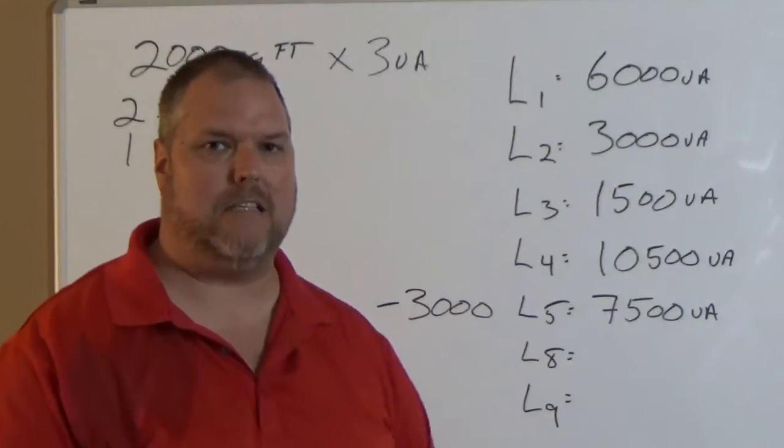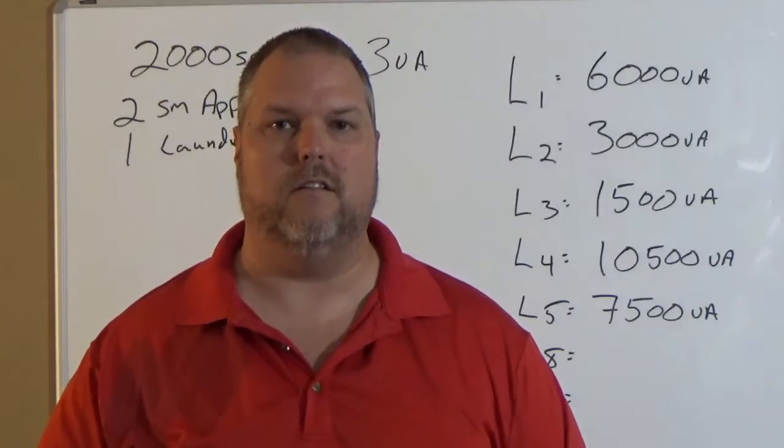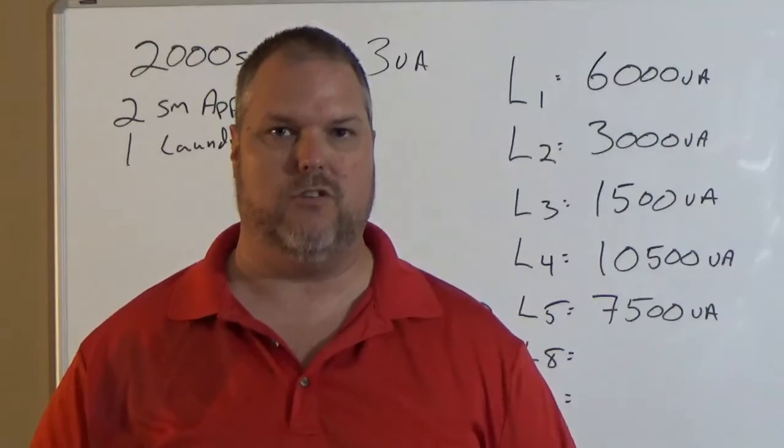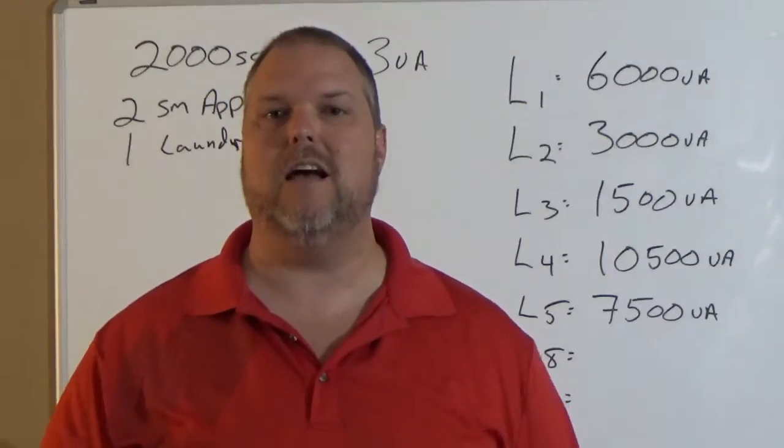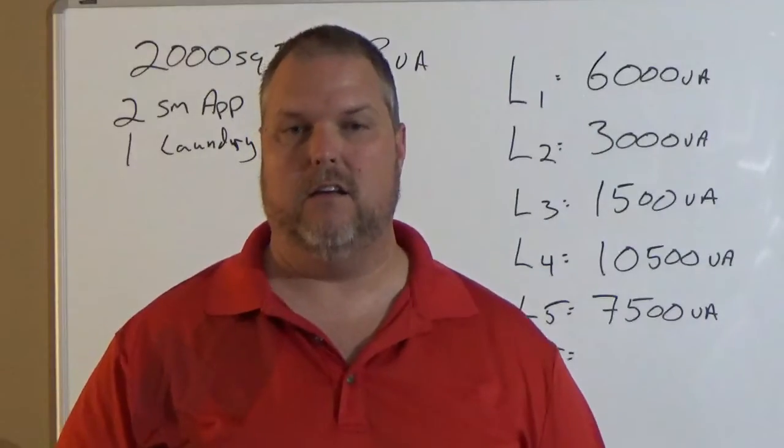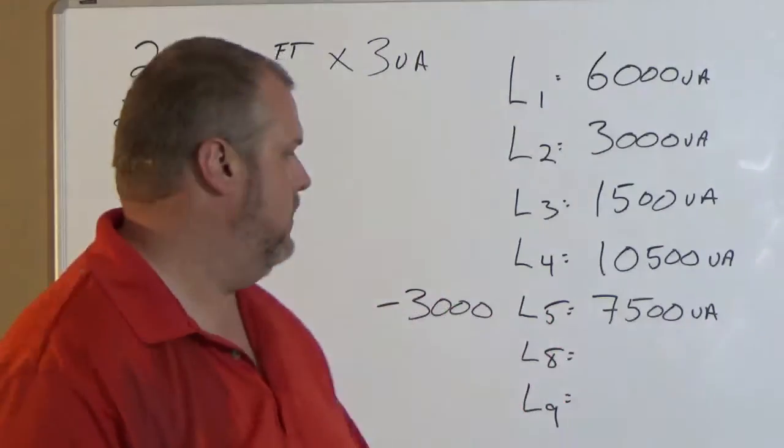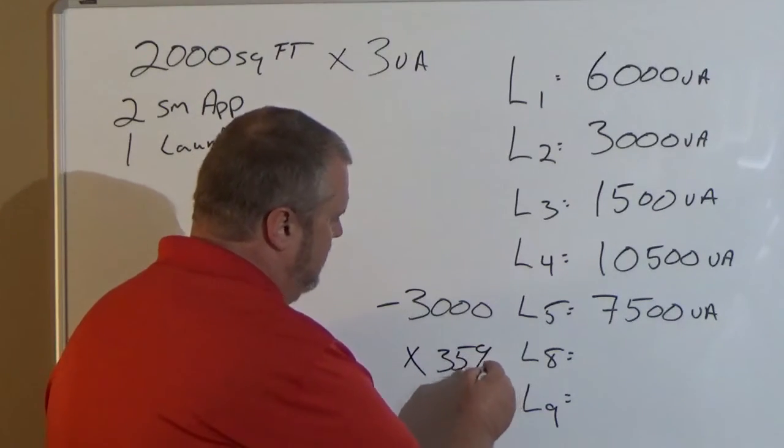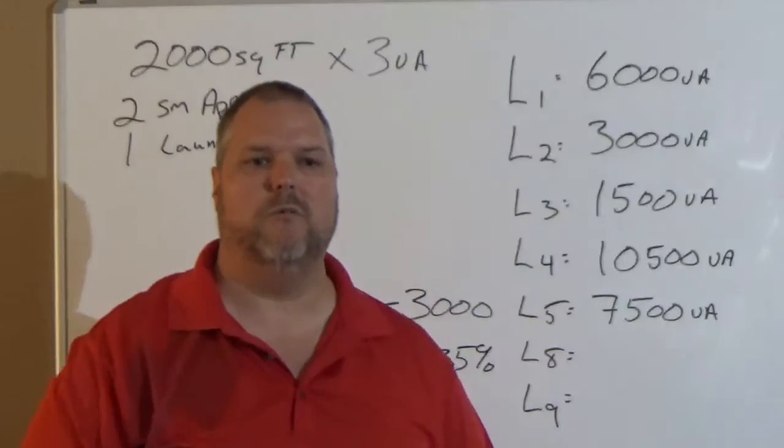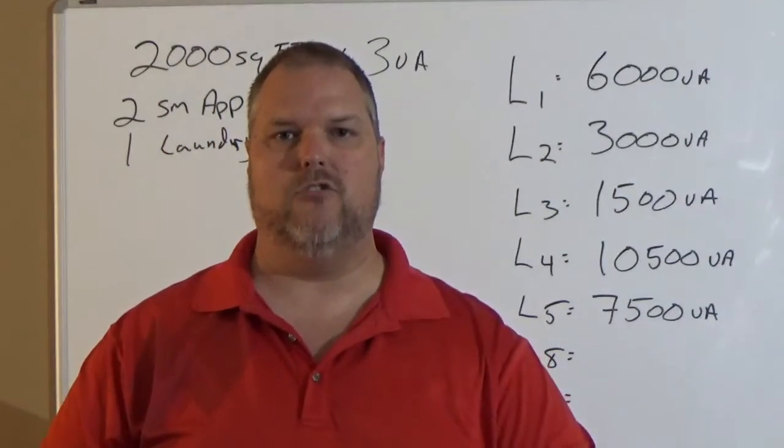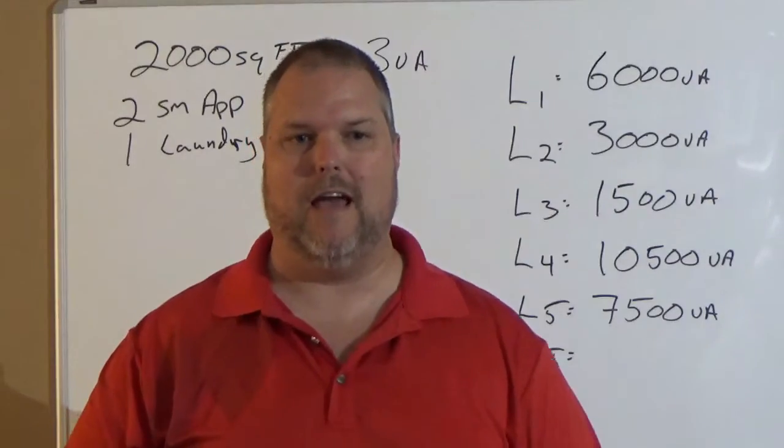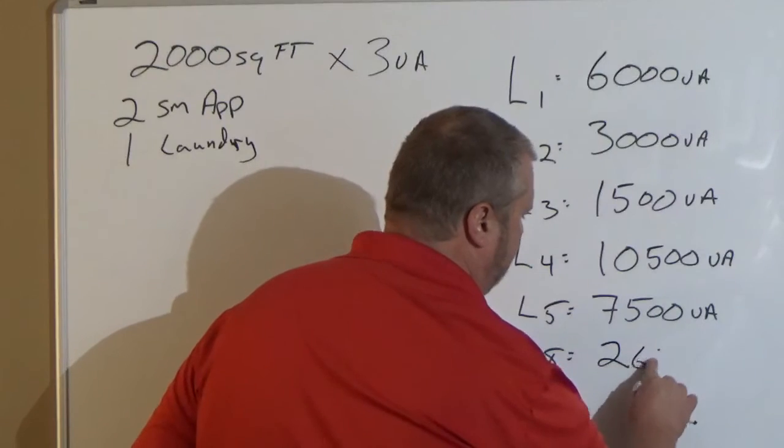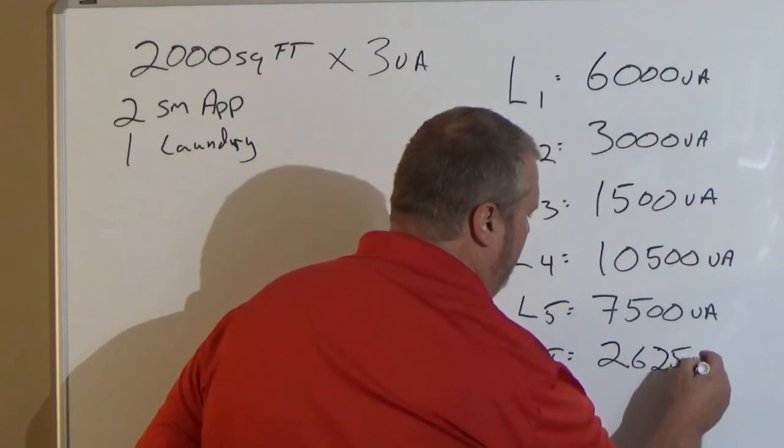We're taking 3,000 from 10,500 because that's our first 3,000 at 100%, that's going to leave us with 7,500. I skip line 6 and 7 for a reason. Because we don't have that larger number, we don't have to break it down further. So we're going to go right to line 8. Line 8 is multiply that remainder by 35%. So we take 7,500, we multiply it by 0.35 and we get 2,625 VA.